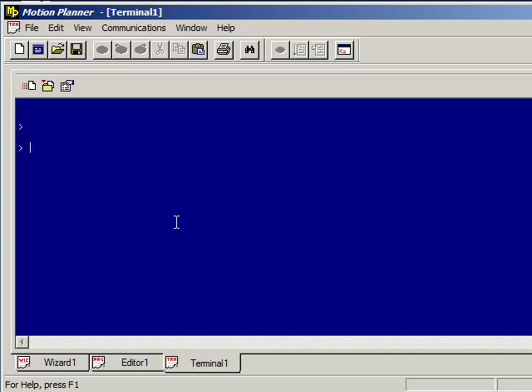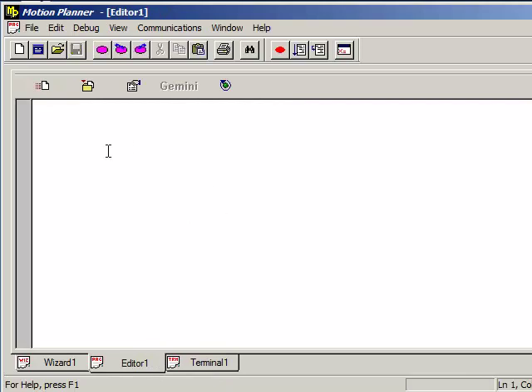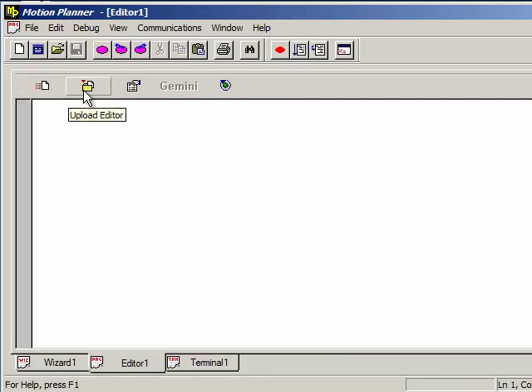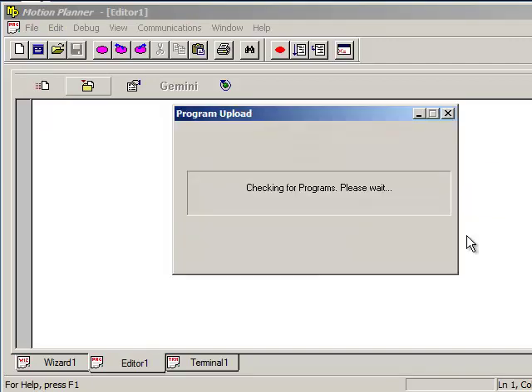And first we want to verify we're actually talking to the 6K. When you first walk up to it, it might be running a program so you hold the Control key and press K. And that will kill the program from running. Typically I do that three times just to verify. Then make sure you're getting a response, type TREV, T-R-E-V and press Enter. This tells you it's a 6K that you're talking to and this is the firmware version. Then go over to the Editor tab and then you can do a Upload Editor. It's just going to warn you that it's going to overwrite what's inside the Editor so go ahead and press OK.